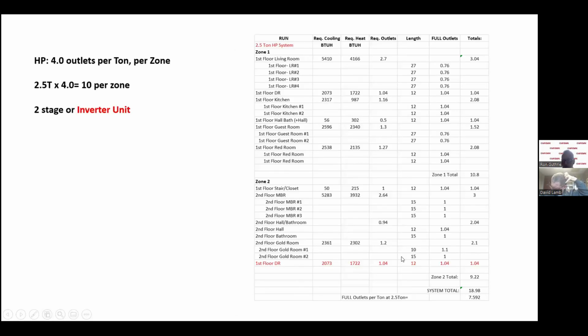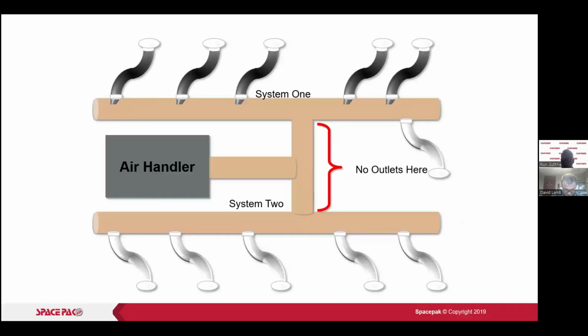Here's actually my house here. The other thing I did was I had a little bit fewer outlets upstairs in my zone 2. So what I did was I took my first floor dining room outlet and I took the damper off of that. I used the dampers that go on each and every run, not in the 9-inch duct. So I just didn't put a damper on that. So that particular outlet works on either zone. Okay, so what that did was it made my zones a little bit more even anyway, 9.22 versus 10.8. All right, I ended up with 7.6. And my system works fine, but it's an inverter system. So I have more than 7 there because I have that heat pump.